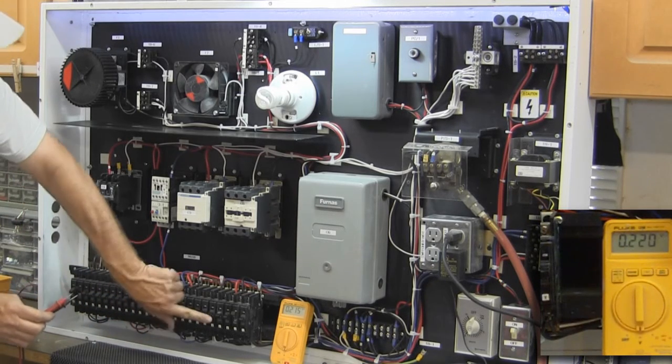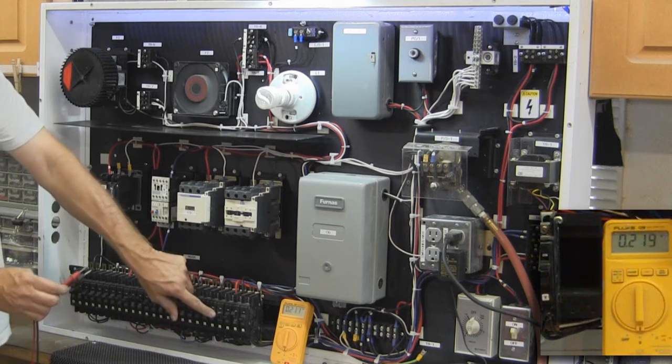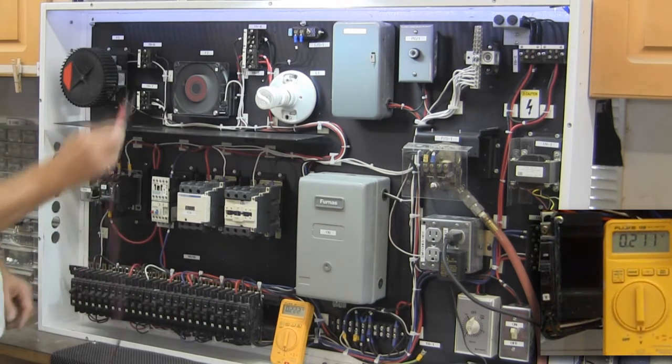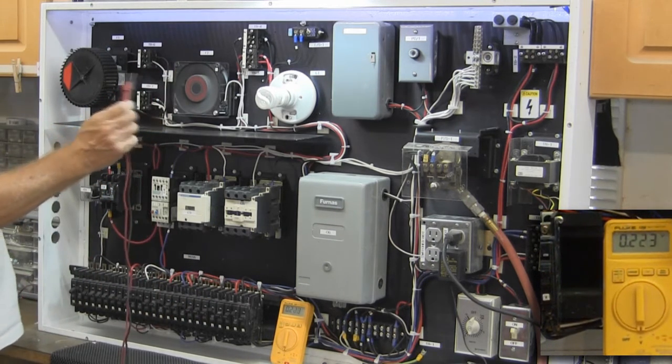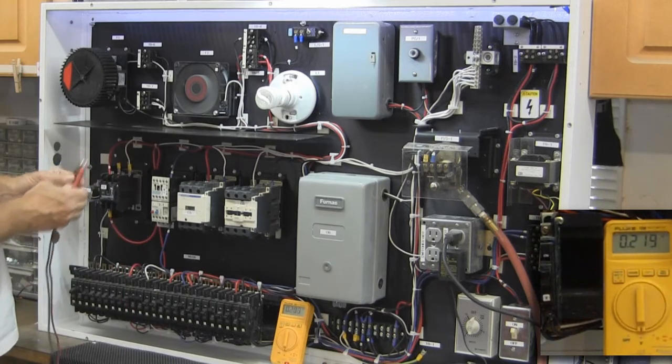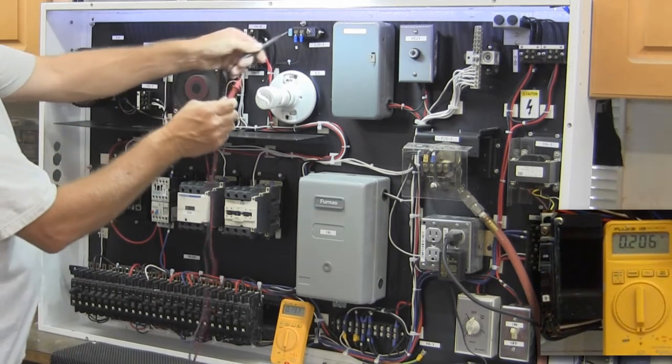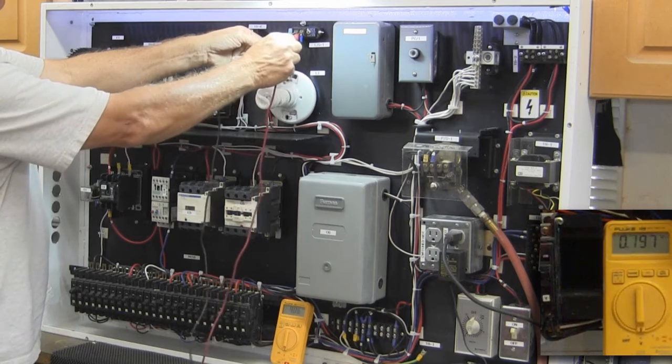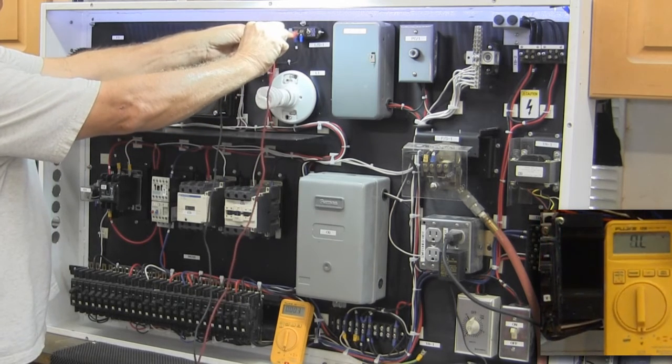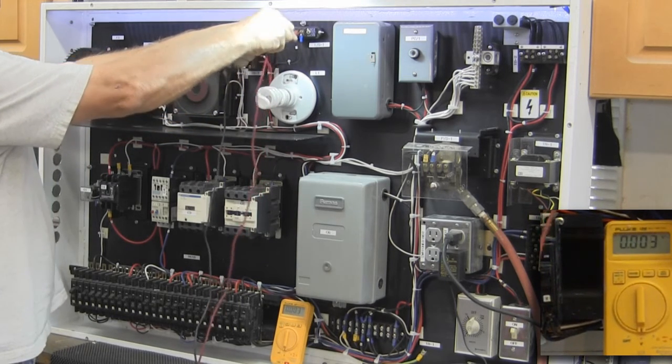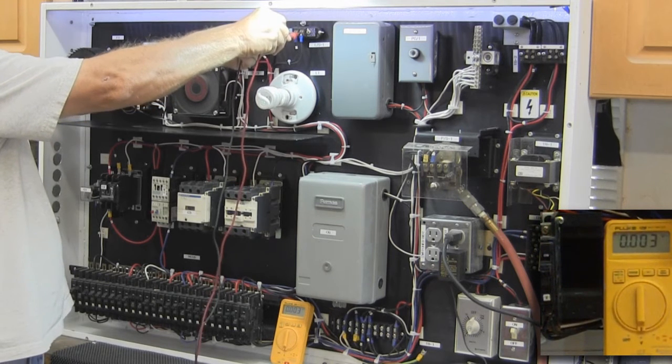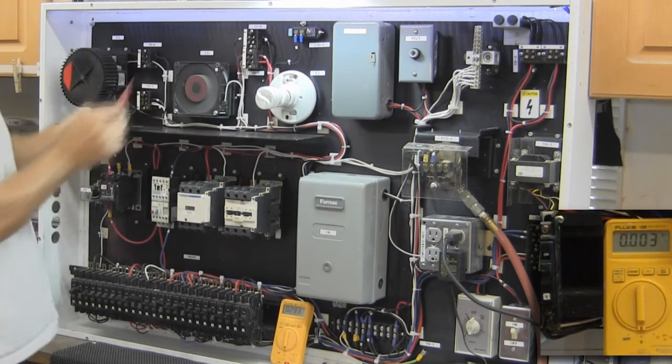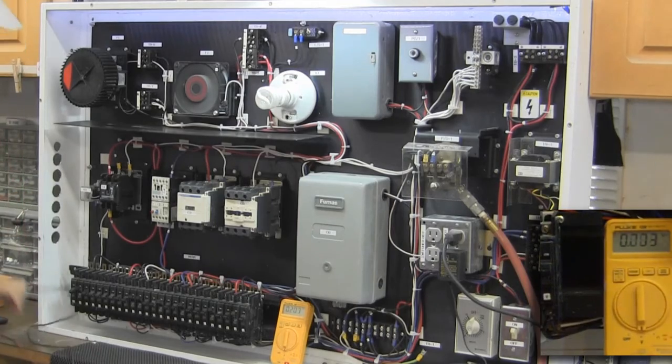And U is right there, we have that working. That's on a limit switch. The limit switch has only two hots, so if I go between the two wires, the hot and switch leg on the limit switch, I'm not getting any voltage. Now watch what happens when I adjust that limit switch.